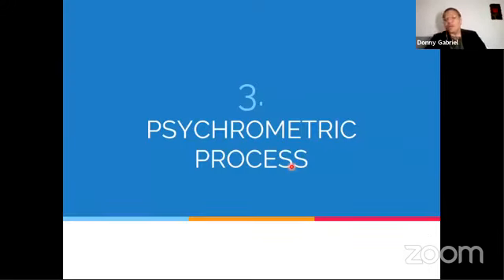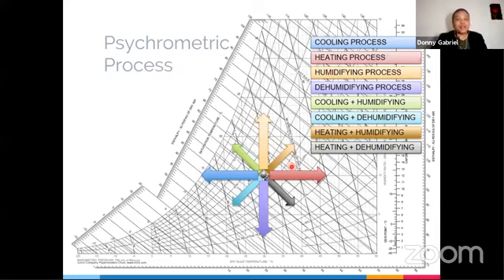Next, we will go to our psychrometric processes. All right, psychrometric processes. There are a few: a cooling process, heating process, humidifying, and dehumidifying. These four are the main psychrometric processes. Cooling, heating, humidifying, dehumidifying. If from one point you have a psychrometric process that moves this way, it's called a heating process. You would see the dry bulb temperature increases from 30 to 45. So there's an increase in dry bulb temperature. It's a heating process.